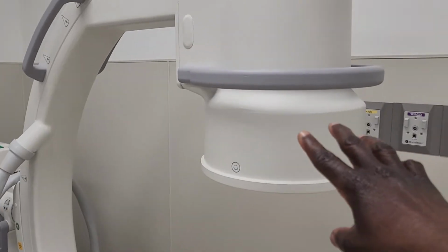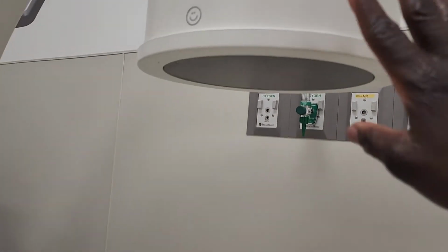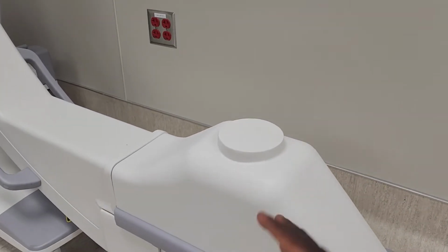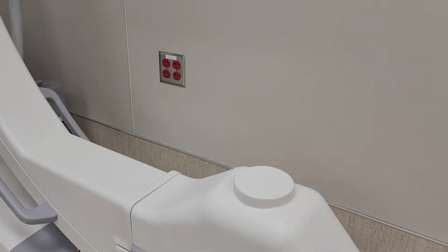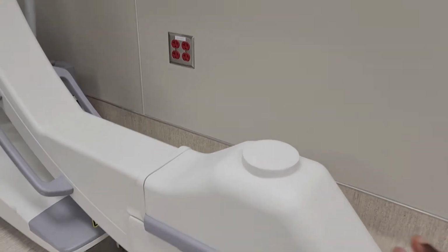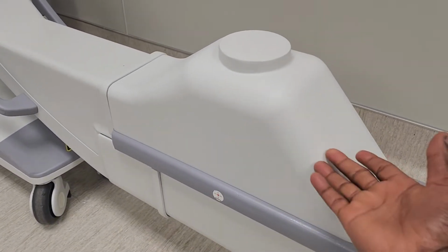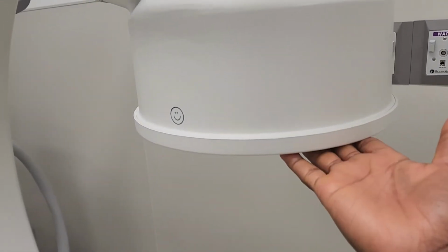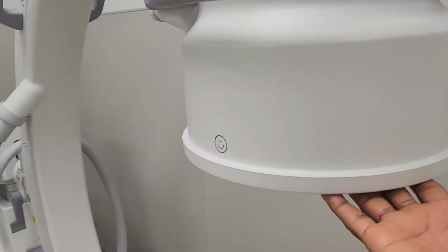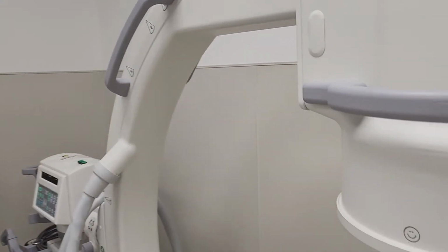So this is a C-arm. This is called the image intensifier, or the II. That's what this part is. And basically, this is the X-ray tube right here. Now, remember, X-rays were discovered in 1895 in Germany. You could talk about the history in our History of Science course, which we'll talk about later. But this is an X-ray tube. It emits radiation, and that radiation then comes to the image intensifier, and then those images show up on a computer monitor, just like your standard computer monitor.